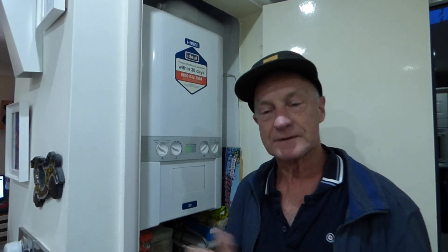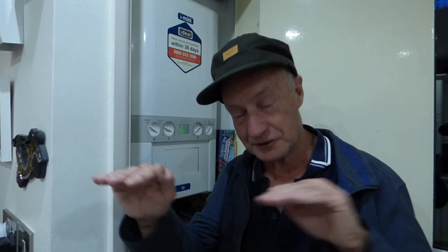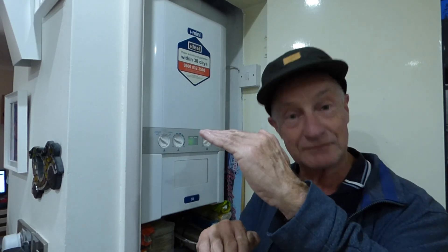On a sealed system with a pressure vessel above the cylinder, you can do the pumping yourself. There is also a workaround: use an upstairs radiator in a bedroom that's rarely used. Drain some water out via the drain valve so the radiator level drops to about a third, then repressurize and fill all the other radiators back up — but leave that one radiator with the lowered water level. The air in the top five or six inches of that radiator then acts as an expansion vessel, doing the expanding for you.